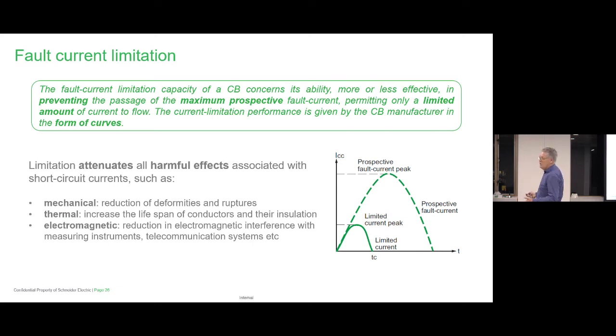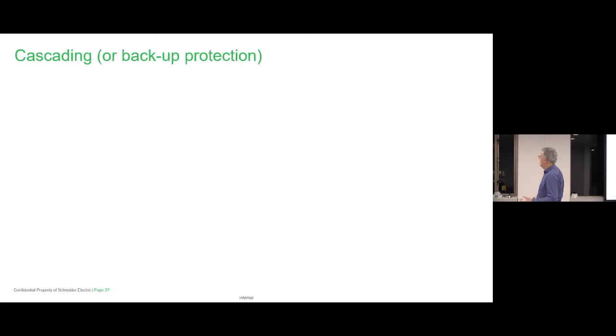So if you can do that, then you can go another level, and this brings us into cascading. Because of that principle alone, the ability of that breaker, we have been able to introduce a concept that has always been around, cascading or backup protection, in the fuse world. Before circuit breakers even existed, we had fuses where the upstream was bigger and hopefully sat there, but if it didn't, it might pop. But we didn't end up with selectivity or discrimination. But with circuit breakers, we were able to do both selectivity and also reinforced breaking capacity.